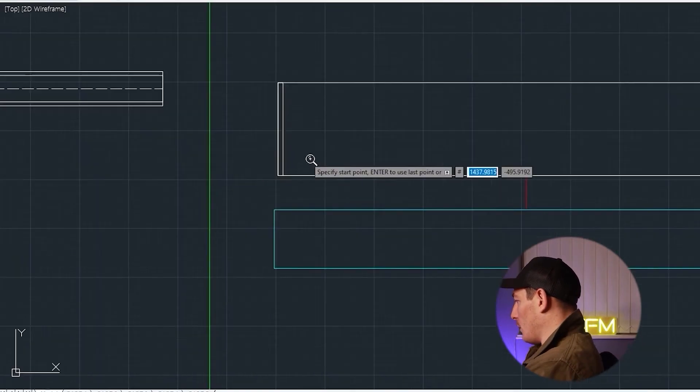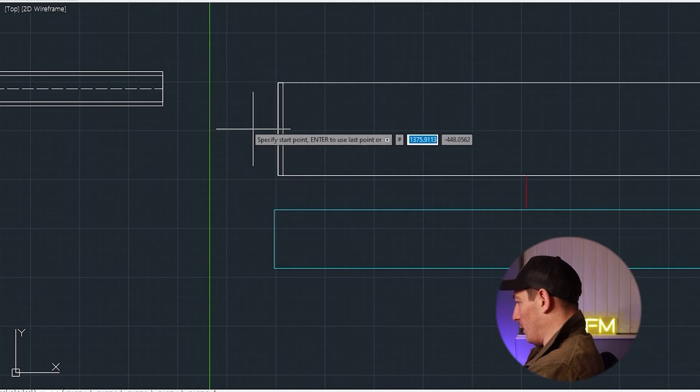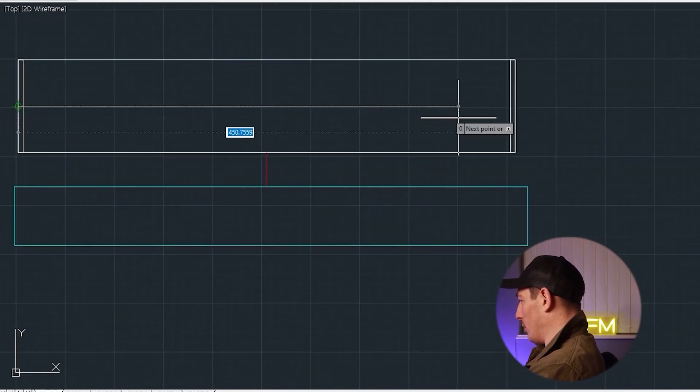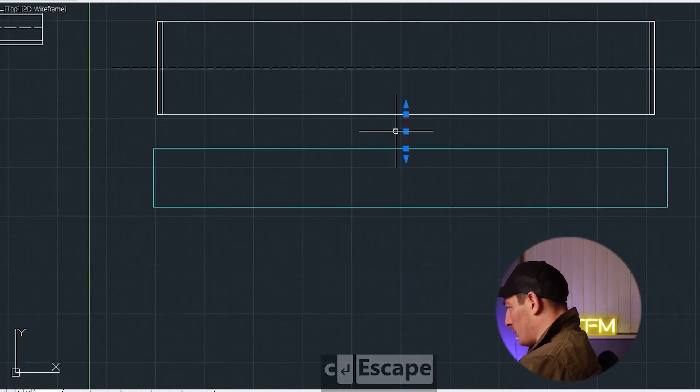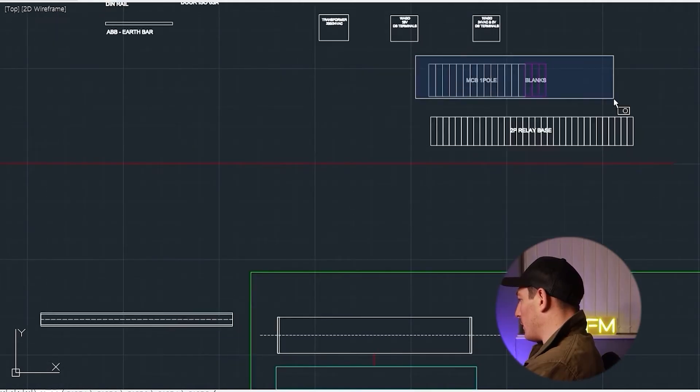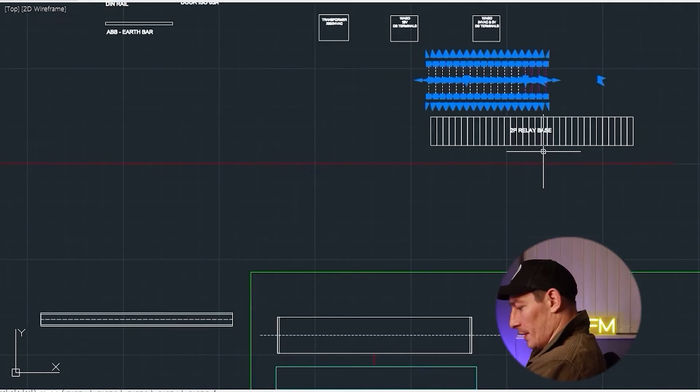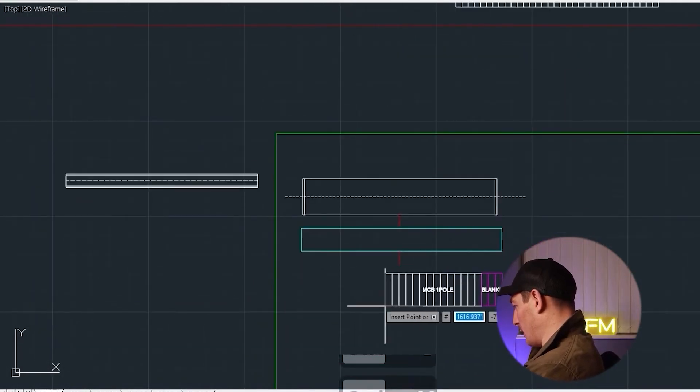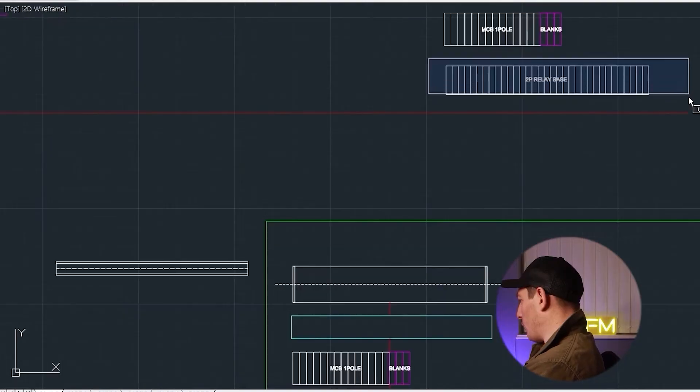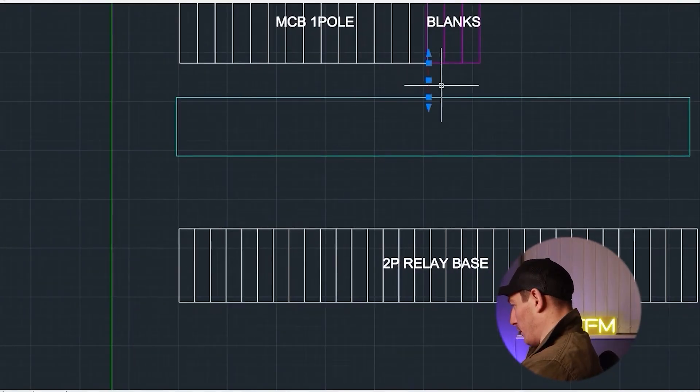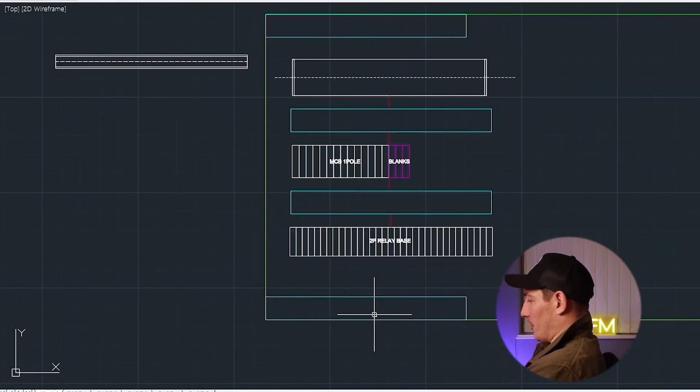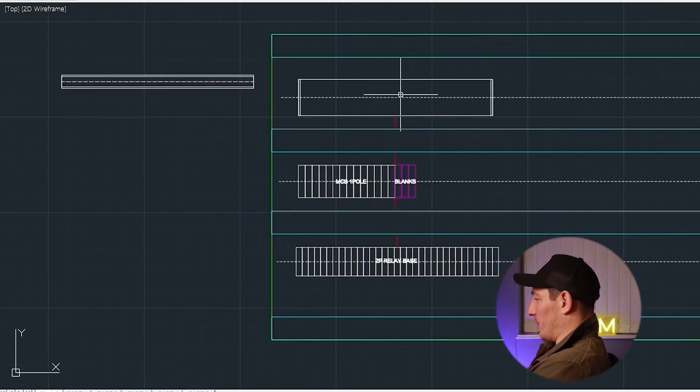So the next thing here there'd be a bit of trunking. So let's have a look what we've got over here. Let's go with the 60 by 80 to start with. Copy that, and let's rotate it, let's make that blue. I'm also gonna just add a center line through the terminal blocks here. Let's copy our spacer again. I'm gonna put the MCBs in, see what that looks like here, another bit of trunking. Now our relays, put a spacer in there. I'll add a bit of trunking at the top and the bottom as well.